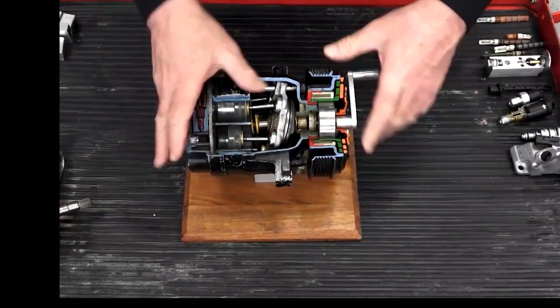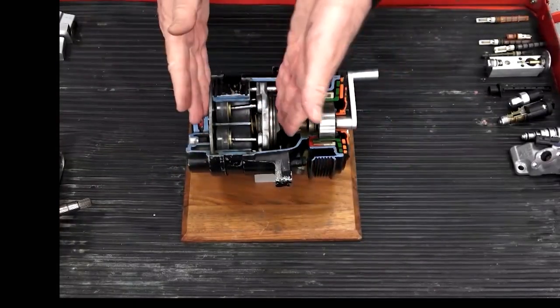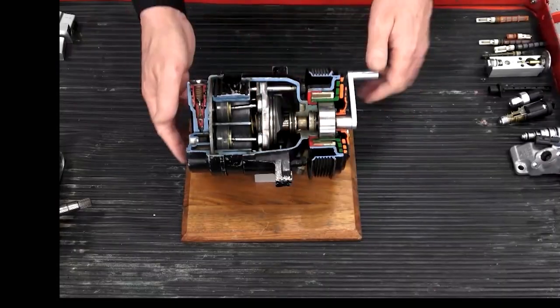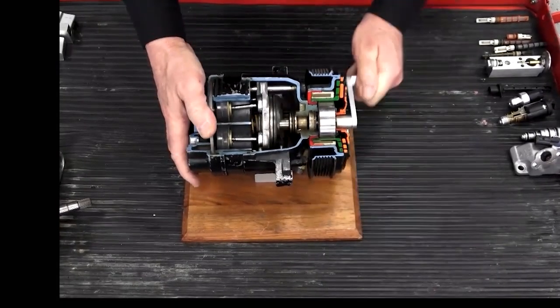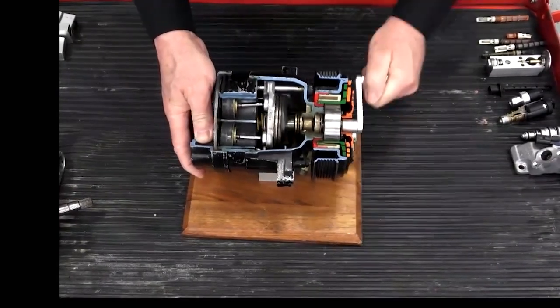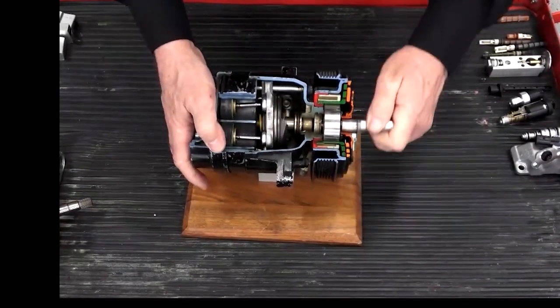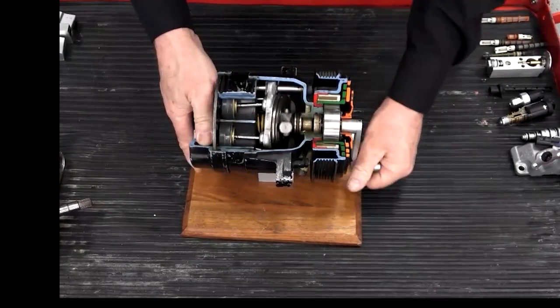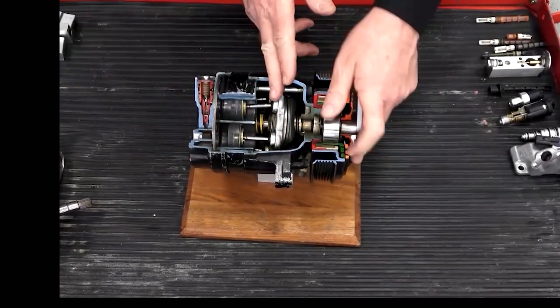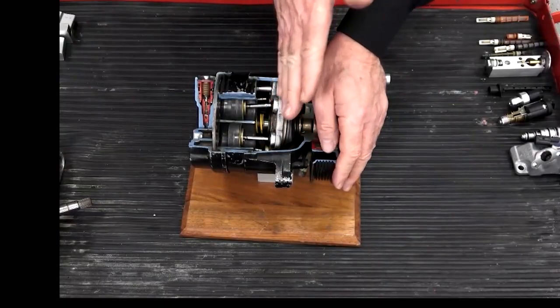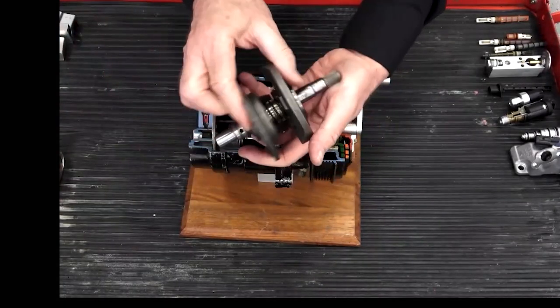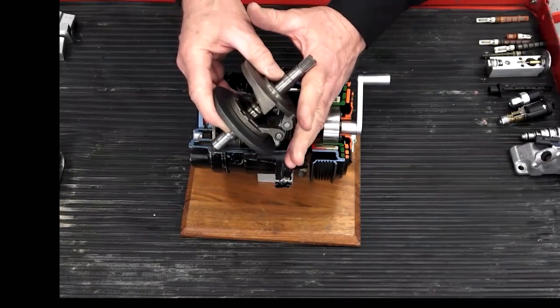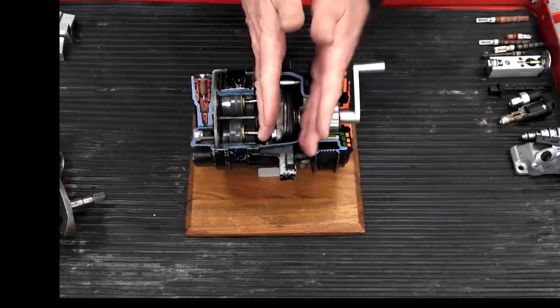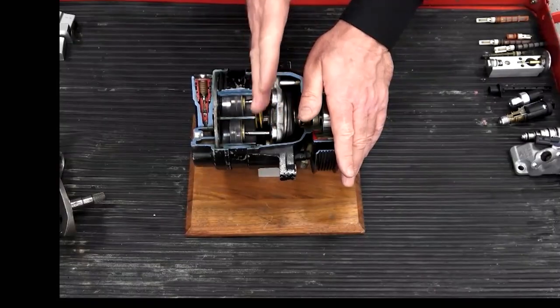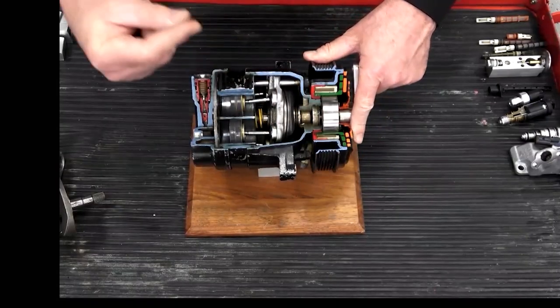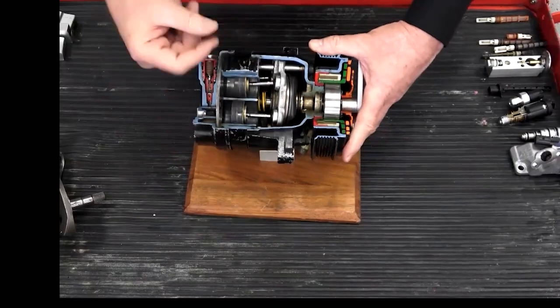So if I position that hinge like that and now change the angle, see how I've changed the angle of the wobble plate to right angles of the crankshaft. Now if I turn this compressor, watch the pistons there, they hardly move at all, right? And if I put it somewhere in the middle, then I'd have a medium stroke. So the whole idea is, by controlling the angle of the wobble plate, or the swash plate on a more modern design, I can literally control the pumping. I can seamlessly, smoothly, gradually change the pumping displacement of the compressor on the fly, just to match the heat load on the system.